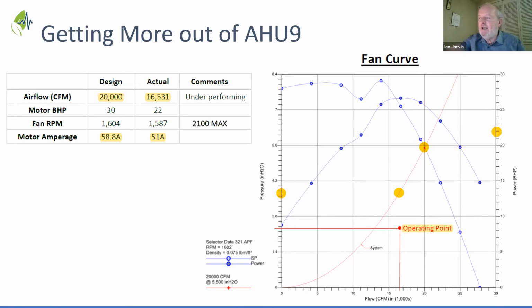But let's say if you track this any which way, nothing lines up. The unit's using way too much power for the amount of air it's producing. Its static pressure is low, and it's not anywhere close to the original design curve. So Simba, with this picture, if you had your druthers, what would you have done so that AHU 9 was ready for the project that you have in play right now?